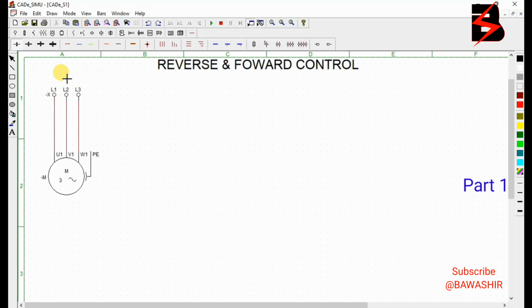So here you will see that line 1 is going to coil 1, that is U1. Line 2 is going to coil 2, that is V1. And line 3 is going to coil 3, that is W1. This is V1, W1. So when we try to run this motor, we shall see that the motor is running clockwise. Stop.